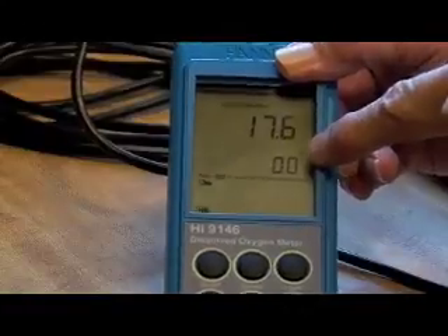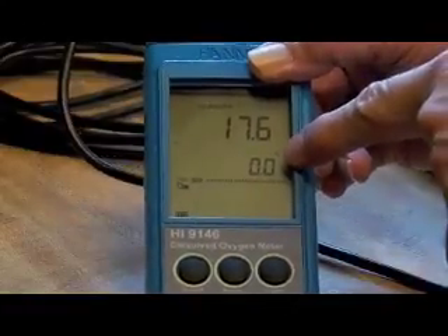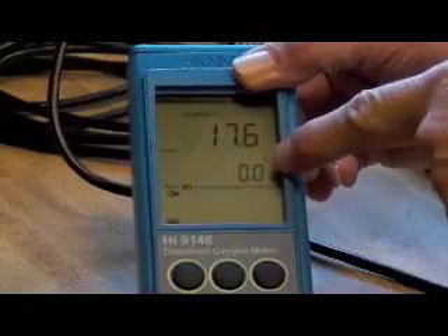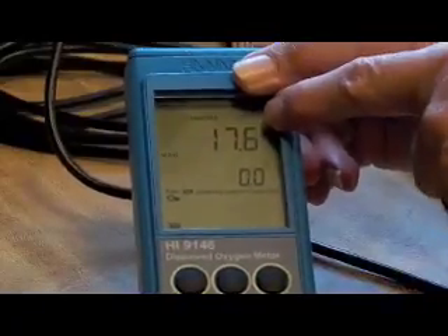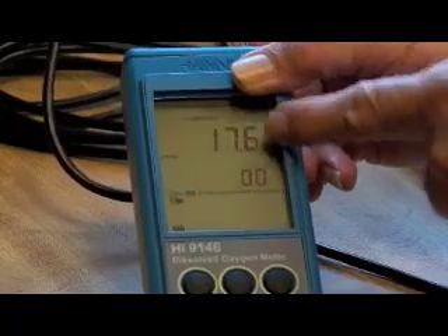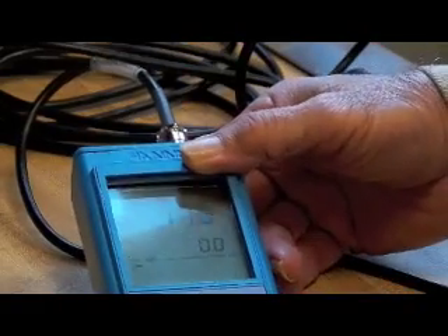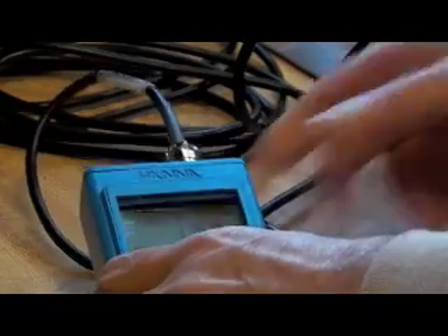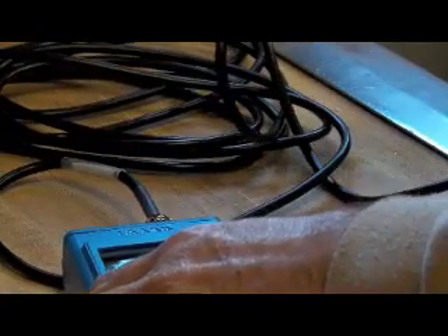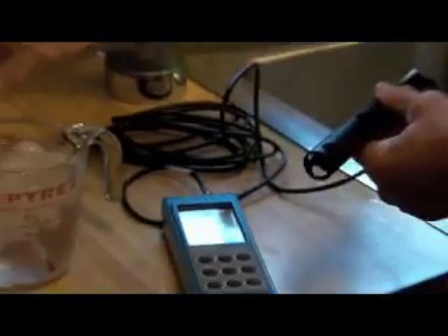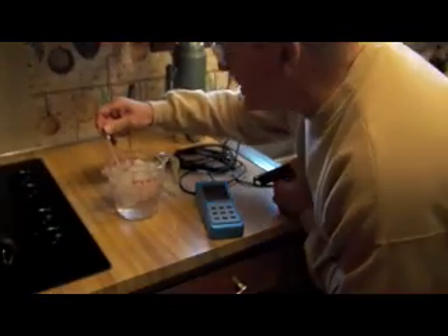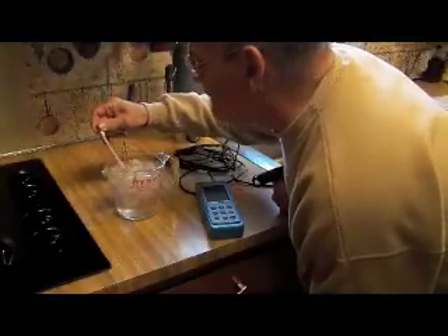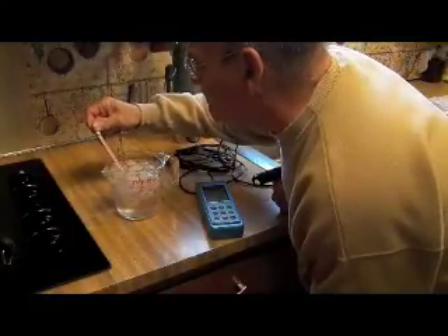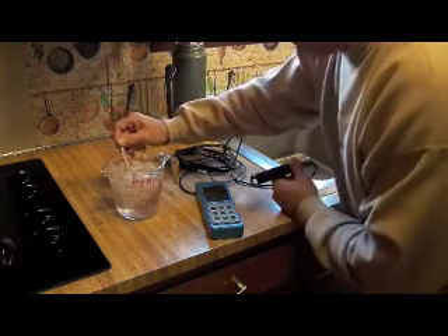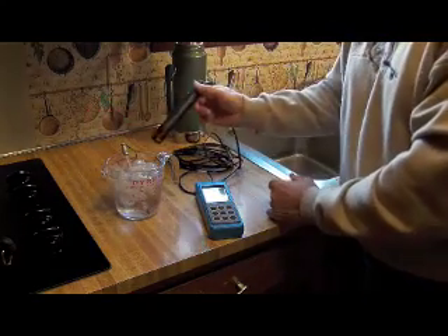We're doing the low temperature, the 0 degrees C endpoint first, the cold water, and we're nowhere near that right now. The probe's sitting at 17.6 degrees, so it's flashing wrong because it's not happy, too big a discrepancy. So, now the instructions at this point say to place, I have my little fishing thermometer in here, you know, and it is reading about 3 degrees or so centigrade.